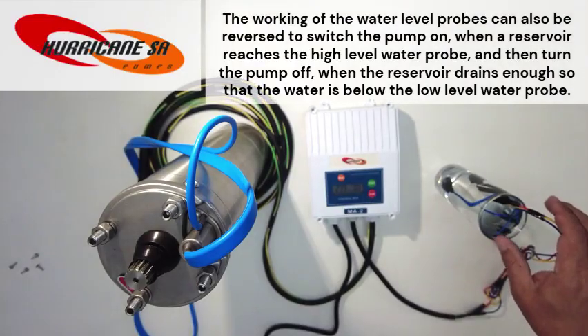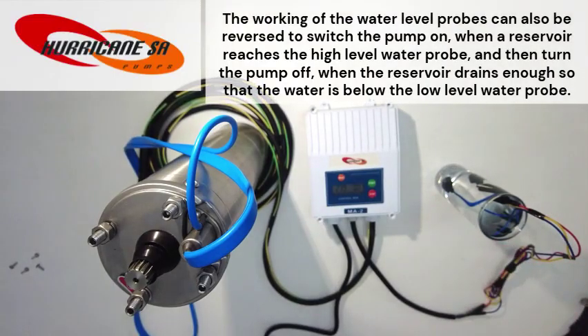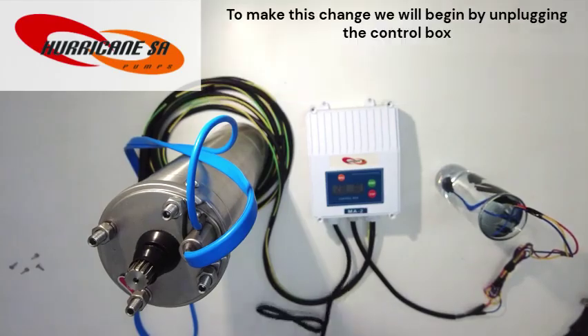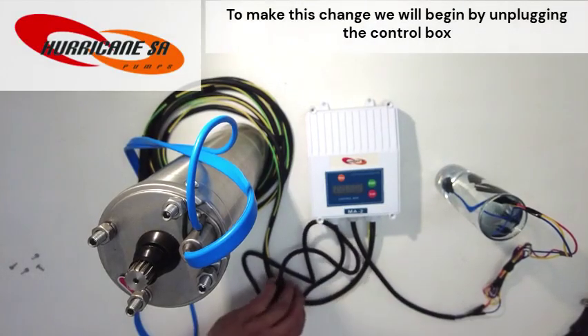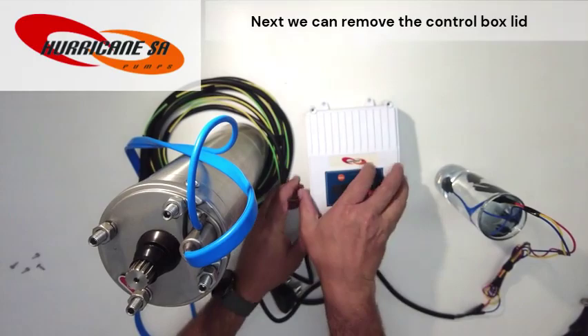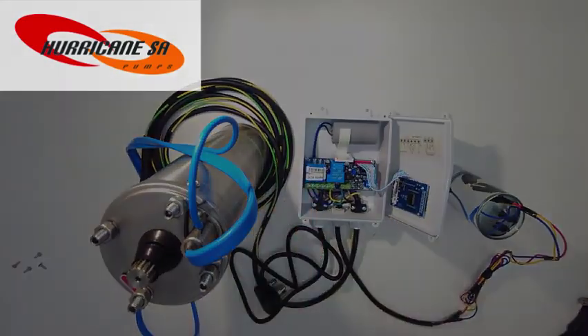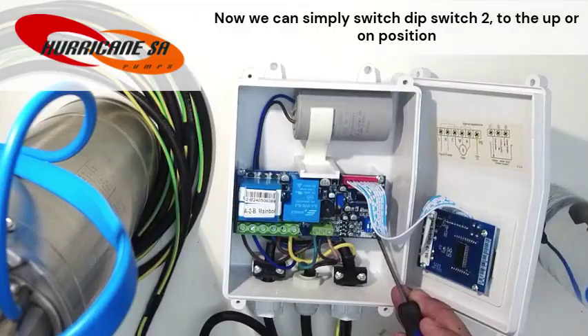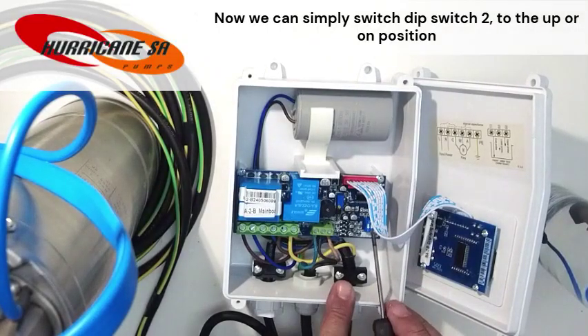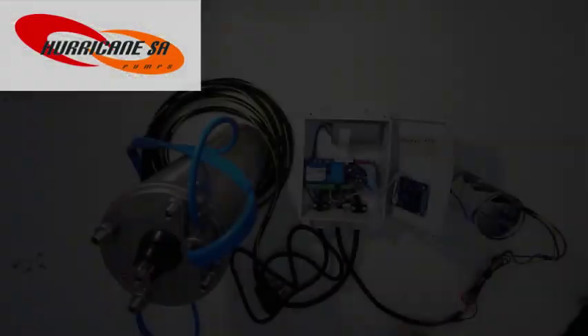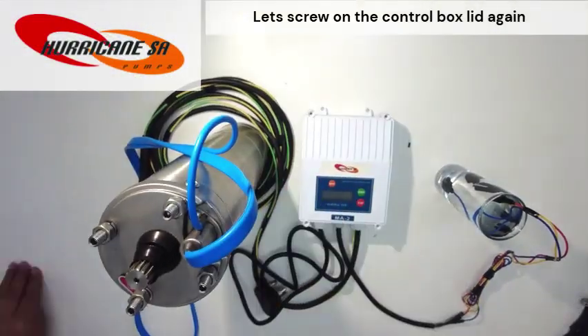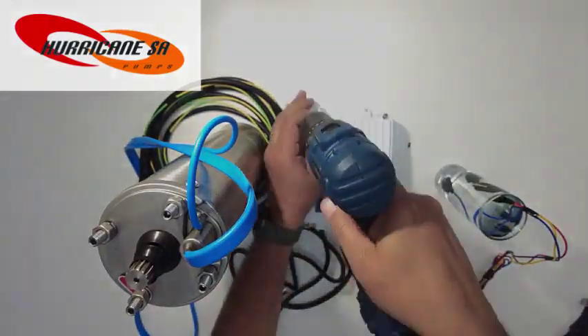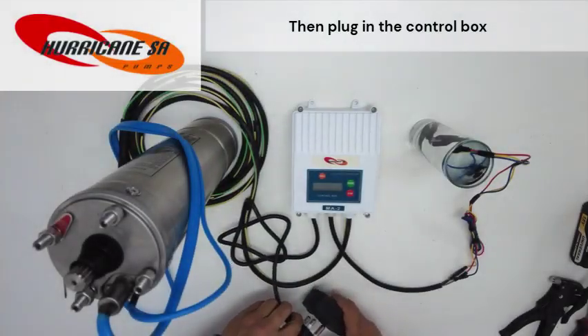The working of the water level probes can also be reversed to switch the pump on when a reservoir reaches a high level water probe, and then turn the pump off when the reservoir drains enough so that the water is below the low level water probe. To make this change, we will begin by unplugging the control box. Next, we can remove the control box lid. Now we can simply switch dip switch 2 to the up or on position. Let's screw on the control box lid again. Then plug in the control box.